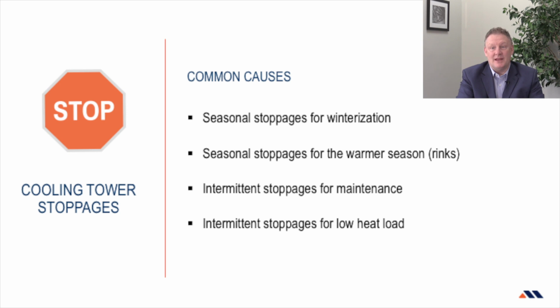Intermittent stoppages for maintenance are also common during certain portions of the cooling season. Even cooling towers used in industrial processes will have intermittent stoppages, usually due to production disruptions. These are obviously much shorter than seasonal stoppages, but will still affect the water quality and impact the system's protection. The technical challenge is to maintain the proper conditions throughout the phase.